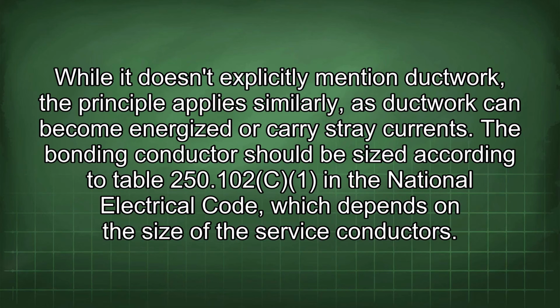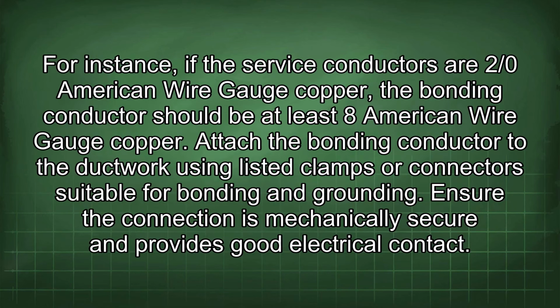The bonding conductor should be sized according to Table 250.102(C)(1) in the National Electrical Code, which depends on the size of the service conductors. For instance, if the service conductors are 2/0 American wire gauge copper, the bonding conductor should be at least 8 American wire gauge copper. Attach the bonding conductor to the ductwork using listed clamps or connectors suitable for bonding and grounding. Ensure the connection is mechanically secure and provides good electrical contact.